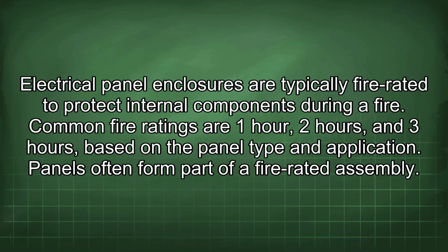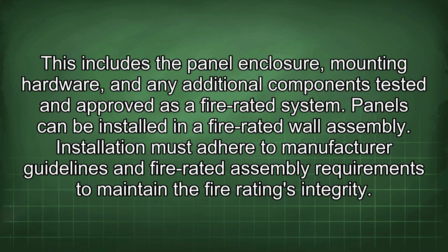Electrical panel enclosures are typically fire-rated to protect internal components during a fire. Common fire ratings are 1 hour, 2 hours, and 3 hours, based on the panel type and application. Panels often form part of a fire-rated assembly. This includes the panel enclosure, mounting hardware, and any additional components tested and approved as a fire-rated system.